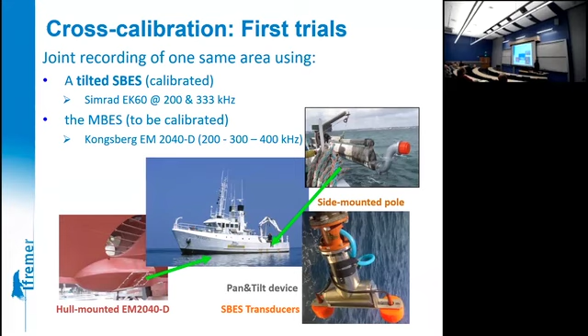Also, we can install several single beam heads on the same plate. And well, that's an example of a result, cross-calibration on carré renard with an EK60 Simrad system, 200 kilohertz, and our EM-2040 working also at 200 kilohertz. And that's the result, and that's not so bad. The single beam data are in green, and the dark line is the multi-beam. And this gives us this calibration curve that we can then apply to the 2040 data.